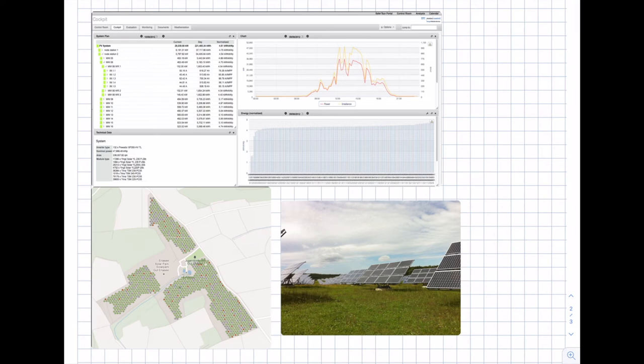You can then investigate whether the issue is due to a data communication problem or a technical fault in the inverters or modules. The bottom visualization shows a map of two-axis tracking systems installed in southern Germany — green means everything is fine, red means an issue has been identified, and grey means work is ongoing. This map helps localize issues and direct the technician to the right location.